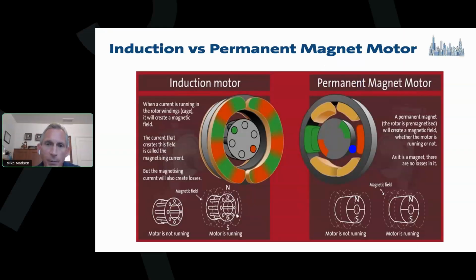So first advantage, all of these are ECM circulators, permanent magnet circulators. On the left with a conventional induction motor, we're using the electric magnetic field that's created with the alternating power to induce a magnet in the rotor. And that process is not very efficient. So inducing a magnet in the rotor is not as efficient as it could be. By having a permanently magnetized rotor, that's one of the things that makes these ECM motors much more efficient.